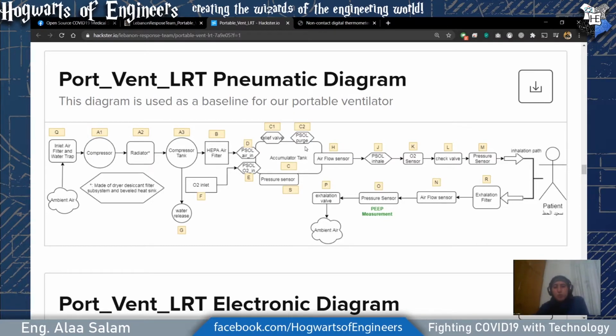Another thing we need to observe is the pressure inside the accumulator tank. This is how we know that we have some sort of loss of air or oxygen. We have sensors to tell us, hey, you need to pay attention, we have a problem here. The sensors at the PSOL levels identify what percentage of oxygen we're using. This is a setup sensor, so we cannot rely on it to identify if the amount of air and oxygen going into the accumulator tank is correct.